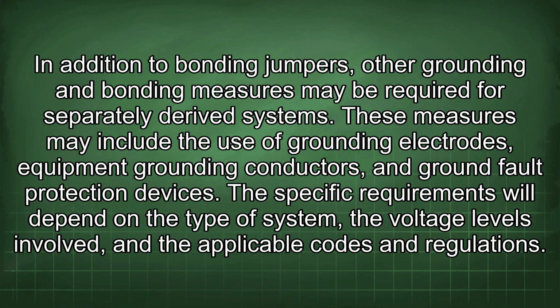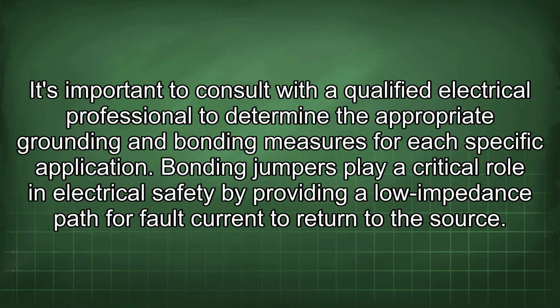In addition to bonding jumpers, other grounding and bonding measures may be required for separately derived systems. These measures may include the use of grounding electrodes, equipment grounding conductors, and ground fault protection devices. The specific requirements will depend on the type of system, the voltage levels involved, and the applicable codes and regulations. It's important to consult with a qualified electrical professional to determine the appropriate grounding and bonding measures for each specific application.